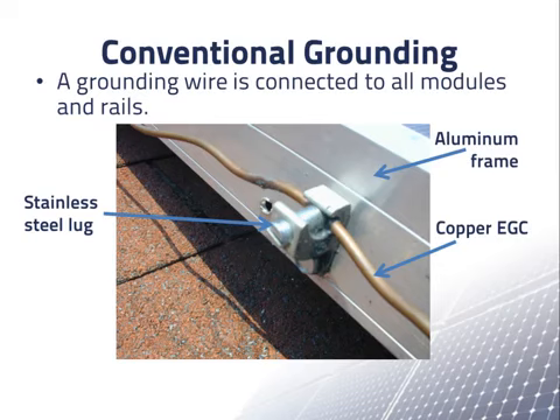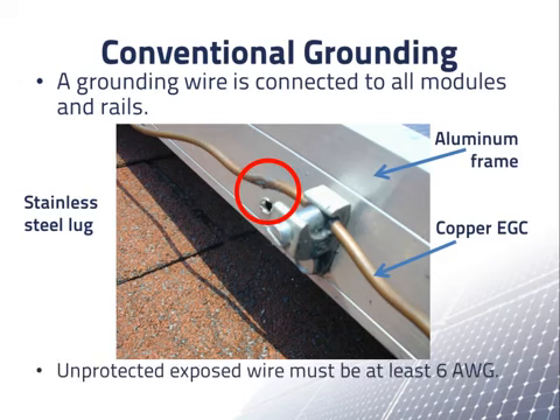The aluminum rails that support the modules also need to be connected to an equipment grounding conductor. It looks like there is a little corrosion here on the copper wire. What may have happened is that the wire was originally connected with an aluminum lug that was bolted using the hole below the corroded spot. Then, when the corrosion was discovered, the old lug was replaced by the one we see now. The uninsulated copper grounding wire is allowed to be exposed here. However, such exposed wire is required to be at least size 6 AWG.